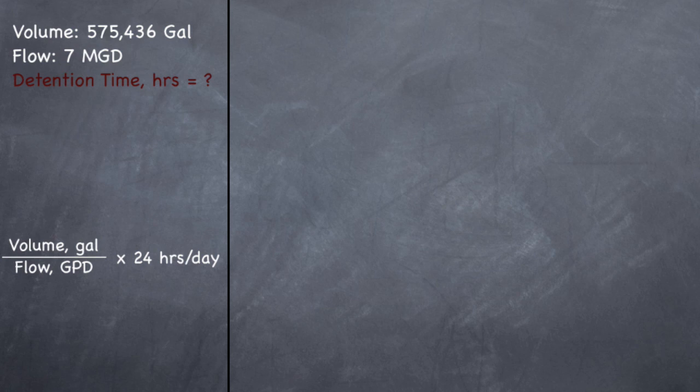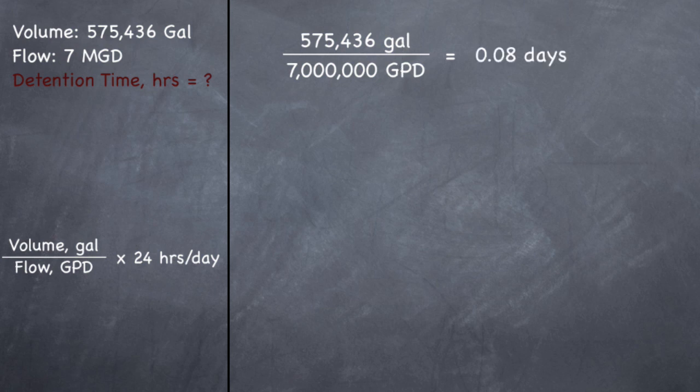So let's write this all out. So we have a volume of 575,436 gallons. And we have a flow of 7 MGD. Now remember, you have to have it in gallons per day. So you need to go ahead and multiply 7 by a million because it's a million gallons per day. And so you wind up with 7,000,000 gallons per day.